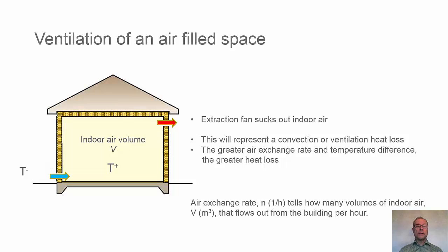So let's say we have an indoor air volume of 200 cubic meters, and if the ventilation fan extracts 200 cubic meters of air during one hour, we will have exactly one air exchange rate, an air exchange rate of one per hour. If it sucks out 400 cubic meters of air per hour, we have an air exchange rate N equal to 2 per hour instead.